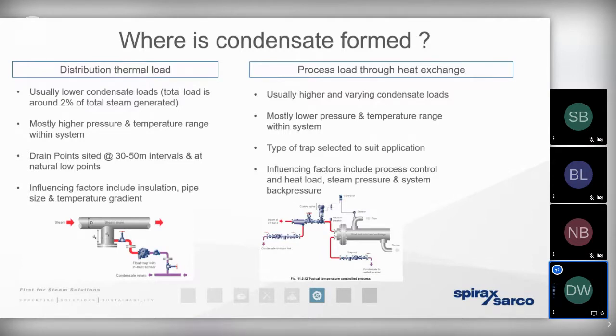Just as we find that there's going to be a greater heat loss when we're warming the system up from cold, the same applies with the heat exchanger itself. We're going to be putting more and more steam into that infrastructure, and it won't necessarily be entering the process. So we're going to get more and more condensate being produced as the process is calling for more and more steam in those initial stages. Without us sizing the steam trap correctly to allow for the warming up load, we're at risk that we could have undersized the steam traps.